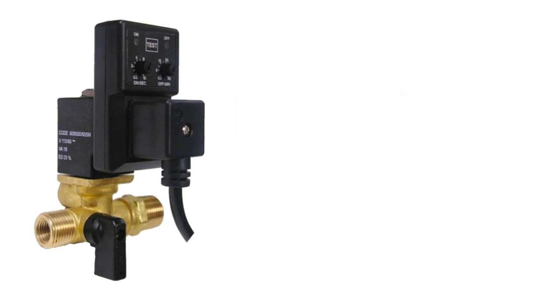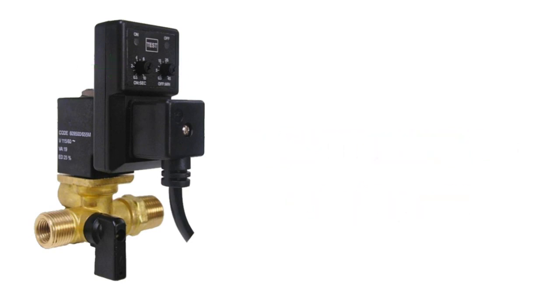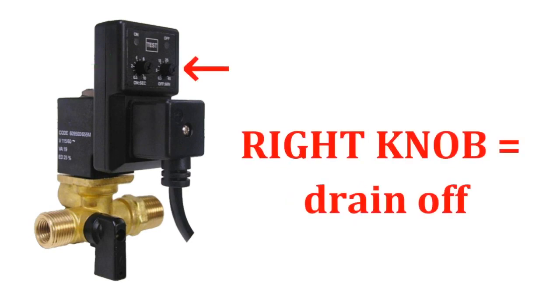To properly set your EDV, use the two adjustment knobs located on the face of the unit. The left knob controls how many seconds the drain remains on or open, while the right knob controls how many minutes the drain is shut off.